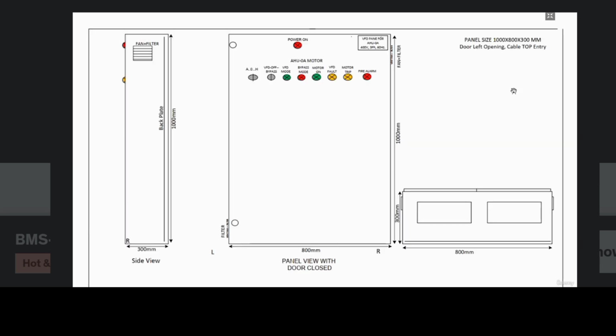This is the outer view of the panel with dimensions and size of the panel. As you can see here, we have selector switches, and also we have indication lamps on the front of the panel. First of all, we have an auto, off and hand switch. Using this switch, you can select to run this fan in the auto mode or in the hand mode. To run it from the BMS, this selector switch shall be in auto mode, or if you want to run it manually from the MCC panel, you shall put this selector switch in the hand mode.